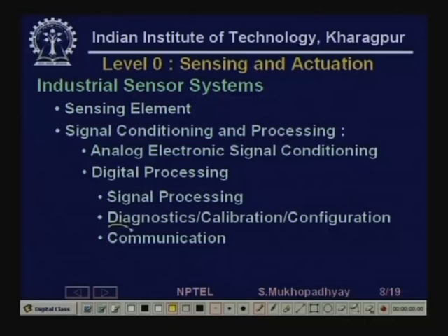So that's diagnostics. Sometimes sensor characteristics degrade. For example, suppose a sensor develops a bias. You can have algorithms to actually detect the bias, and it can do its own calibration. The sensor can send information, or the sensor can be interrogated, and you can find the information that it has developed a bias. So its readings will be interpreted accordingly for greater accuracy.